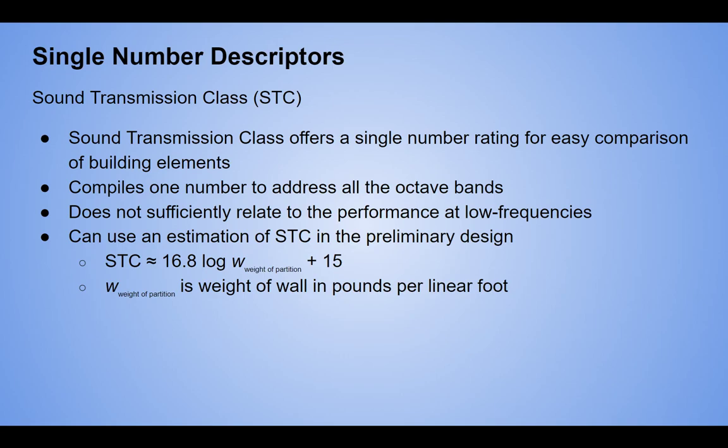A key trend: NC is weighted toward low frequencies, dBA doesn't account for low frequencies, and STC doesn't address low frequencies well either. If you're not considering low frequencies in measurement and not blocking them in isolation design, you'll have a lot of low end transferring from one space to another. You can estimate STC with the formula: 16 log of the weight of the partition plus 15, or more precisely 16.8 log of the weighted partition plus 15.